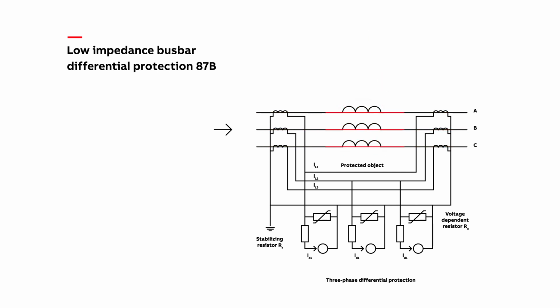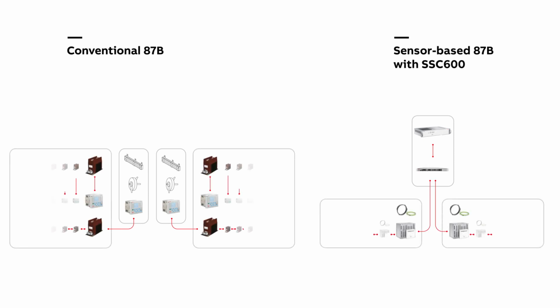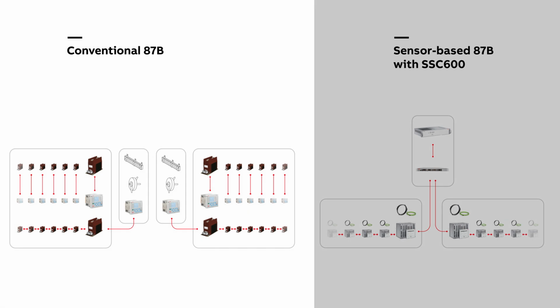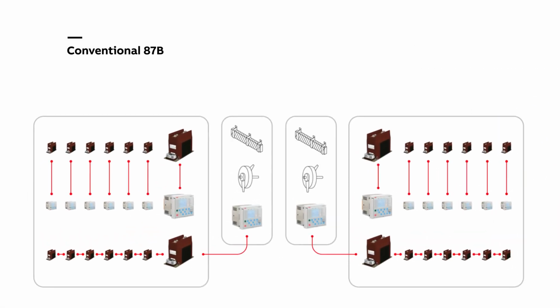In a conventional system, you would need protection relays, varistors, shunt resistors, setting resistors, and other hardware devices for this. Let's look at two examples, two ways to approach this, conventional and with SSC600. Here we have a standard case with 14 panels per switchgear, 7 panels in section A and 7 panels in section B. Both are the same, so for each panel you need standard conventional CTs for the overcurrent functions, which are processed by the protection relay.